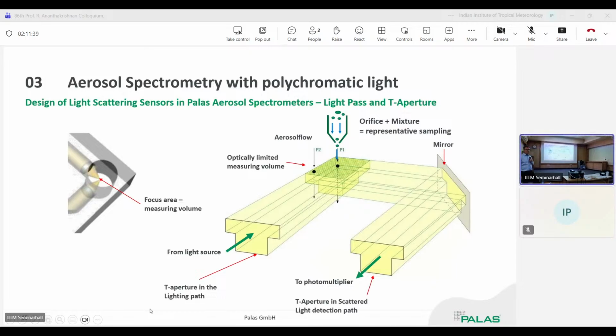Just wondering, because this probe has a very wide particle size range, up to 100 micrometers, as you showed. Yeah. Just wondering, because on the scattering principle, Mie scattering actually works really maybe below 10 micron, because your large angle scattering is more in that range. So for larger particles, forward scattering will be more. So how are things behaving in this case? You're correct. Typically for bigger particles, forward scattering is the solution, but we don't have forward scattering.